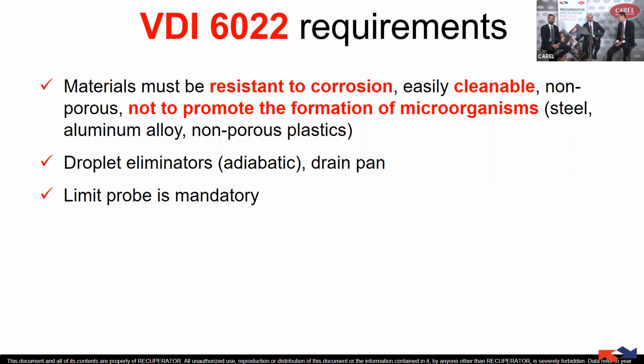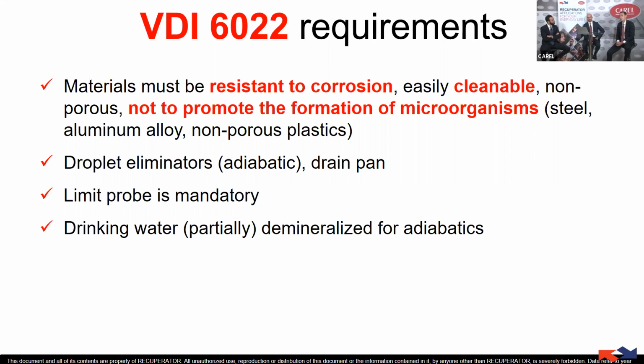VDI also gives some regulations, restrictions and suggestions in terms of controls, because it requires a limit probe. It's a mandatory feature, and our humidifiers and control systems are designed for using this kind of device. It also gives some suggestions on the type of water we have to use: demineralized, drinkable water, especially for adiabatics, because it improves the safety and hygienic condition inside the AHU.